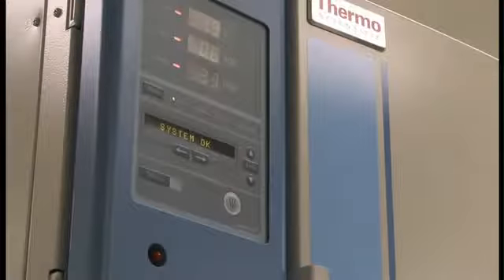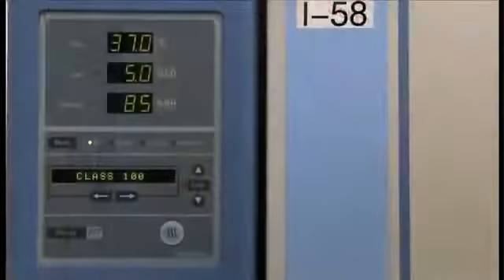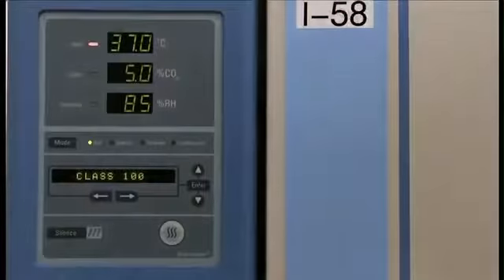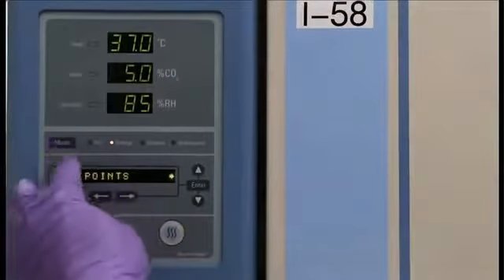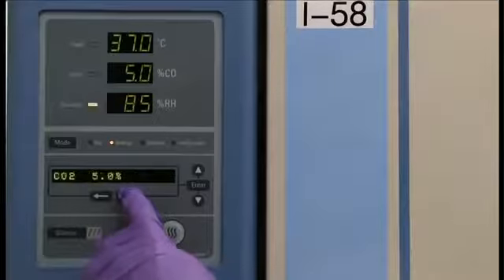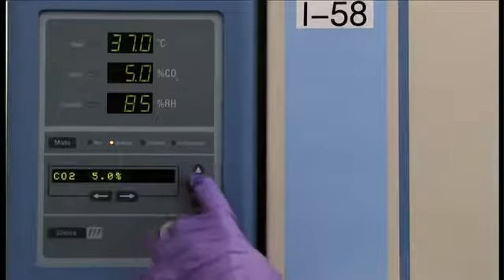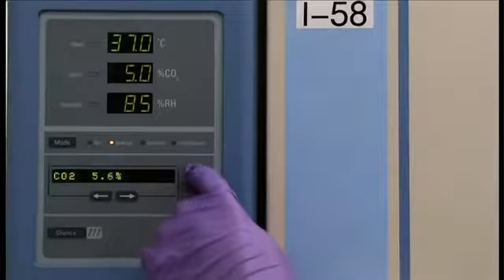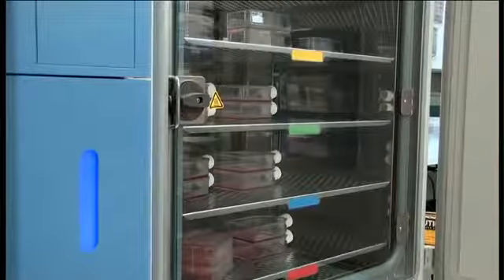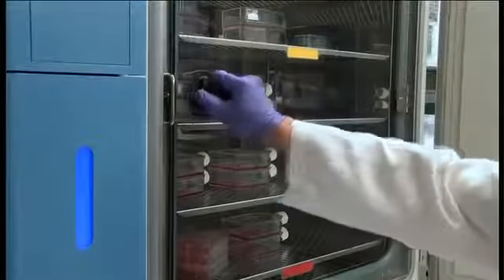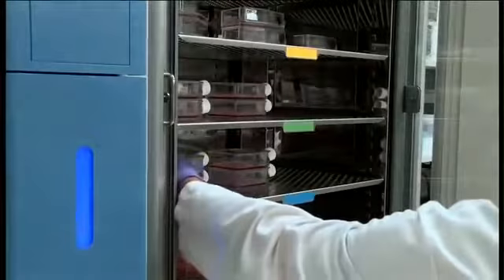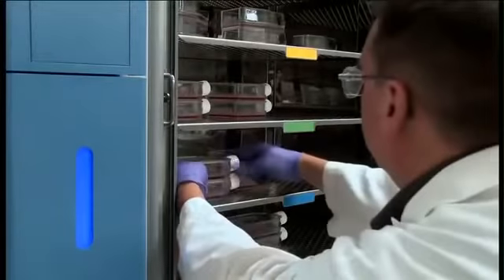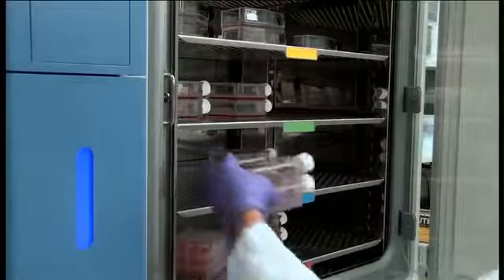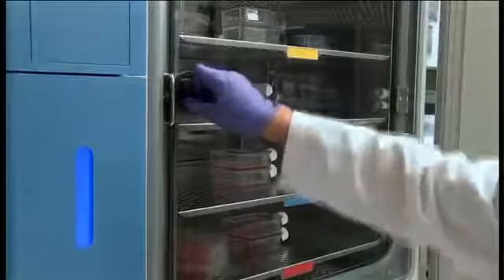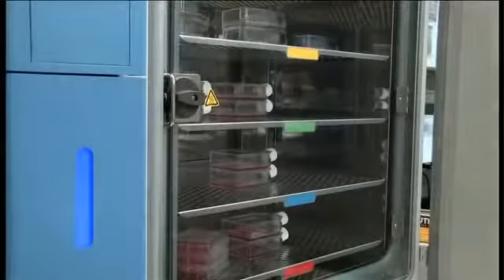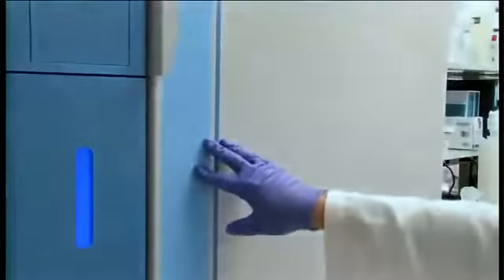Incubators provide the appropriate environment for cell growth. Carbon dioxide and temperature settings depend on cell type and medium selection. Mammalian cells are cultured at 37 degrees Celsius in the presence of 5 to 7% carbon dioxide with high humidity. Inside the incubator, keep your cell culture flasks evenly spaced and avoid crowding to ensure that the air inside the incubator moves freely. This helps to maintain temperature, humidity, and proper gas exchange. Don't make very tall stacks of plates. They may fall over, and lower ones may not get the appropriate gas exchange.